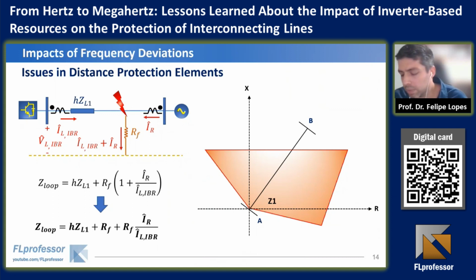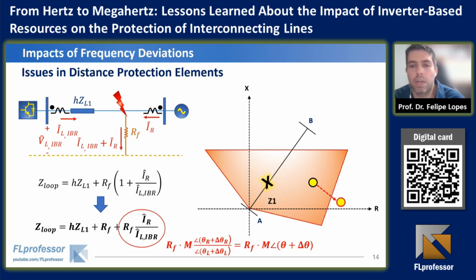To see this problem, we decided to put it in a paper, to write some notes, and to study the problem to better understand it. And basically, we could verify that if the fault is established through an almost purely resistive path, a real value, we have an in-feed effect such that for a fault inside zone 1, for instance, for a distance protection element, the loop impedance is supposed to travel until here, but this real element will move the impedance toward the right side, and then another element will move this impedance a little bit more to the right side with an angle.